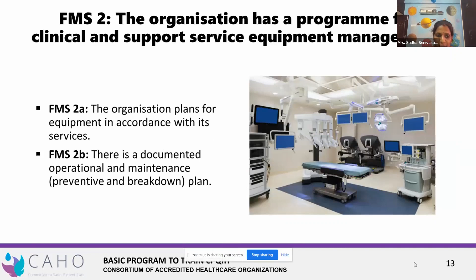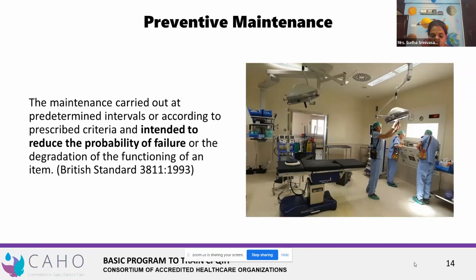What is preventive maintenance? It is an activity done at predetermined intervals, intended to reduce the probability of failure. You do it even before something goes wrong. It is very, very important. In a hospital you will have so many equipments, and unless we plan for it periodically, it's never going to happen. So it is very important to have a preventive maintenance schedule and a calibration schedule for those equipments which require calibration. Apart from that, there also needs to be a system in place to ensure breakdown maintenance.